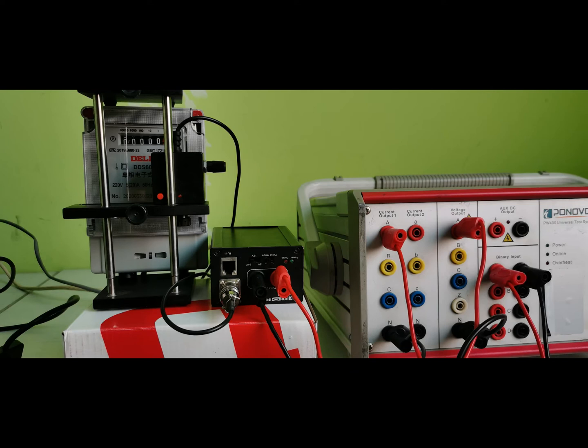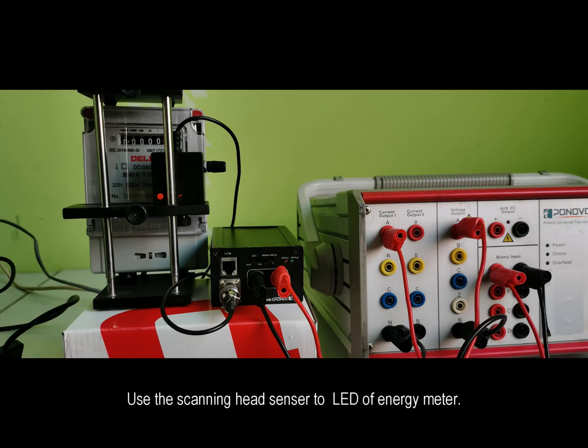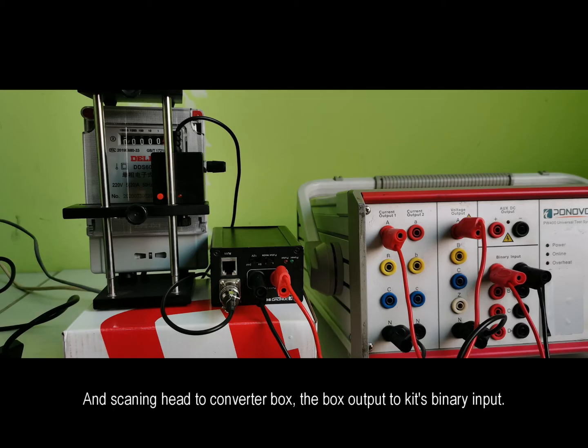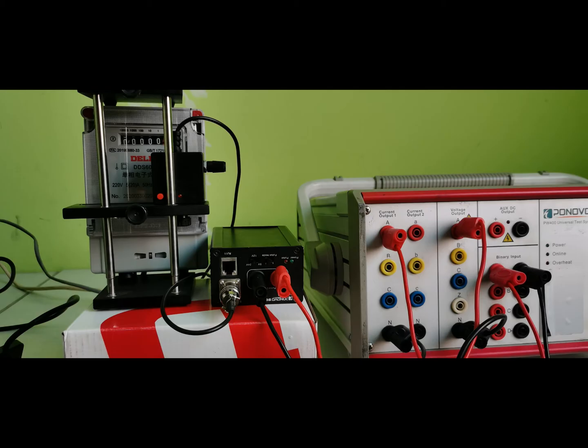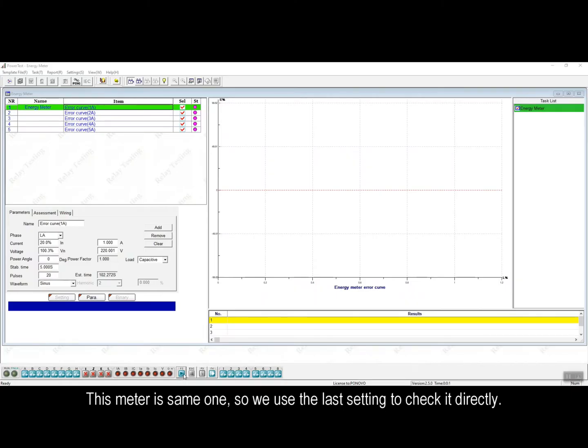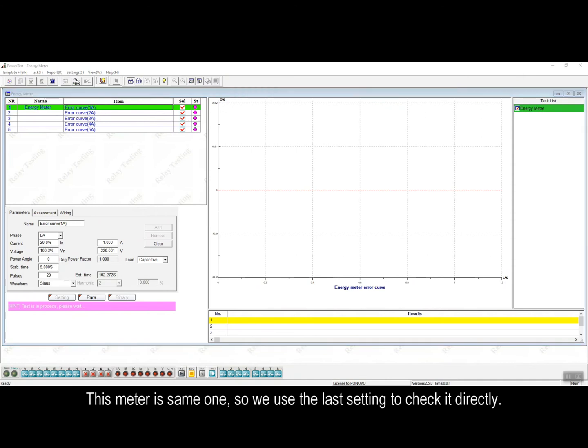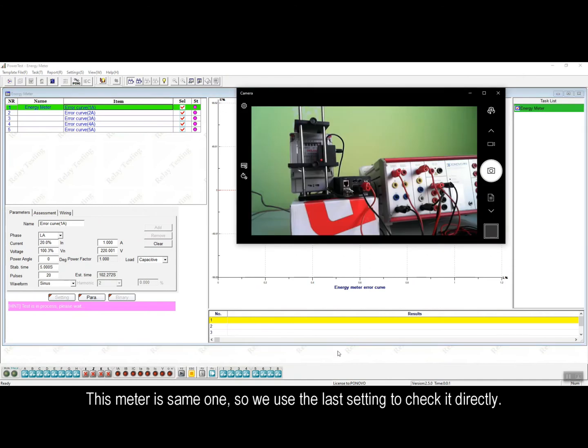Here is the wiring connection between relay test set and PACB108 and the energy meter. We use the scanning head sensor to LED of the energy meter. And the scanning head is connected to the converter box and the converter box output connect to the relay test set's binary input. For this energy meter, we also use the energy meter testing module for the testing.